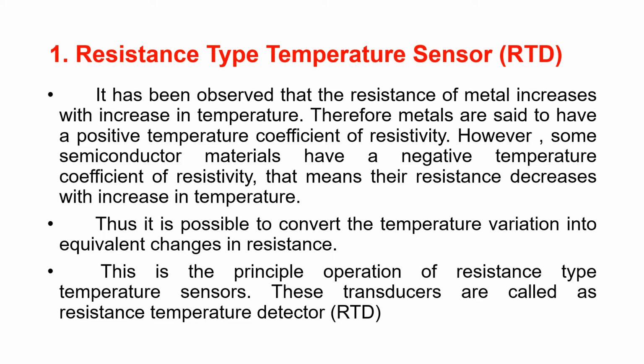It will be either PTC or NTC. If you are using metals, then the resistance will increase if the temperature increases, and if you are using some semiconductor materials, then the resistance will decrease with increase in temperature, that is negative temperature coefficient. Now this is the principle of operation of resistance type temperature sensors, and these transducers are also called resistance temperature detector or RTD.